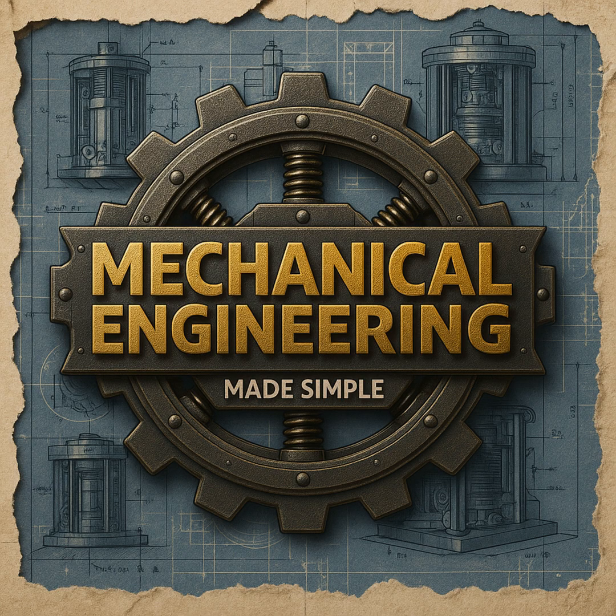And what's the killer takeaway from that formula for a designer? It's the diameter. The pressure drop is inversely proportional to the diameter to the fourth power. The fourth power, so a small change makes a huge difference. A massive difference. If you double your pipe diameter, you cut your pressure loss by a factor of 16. It's a huge lever for designing efficient systems.